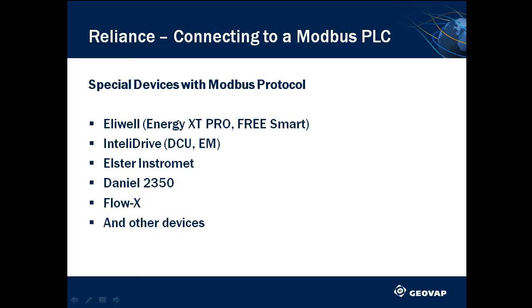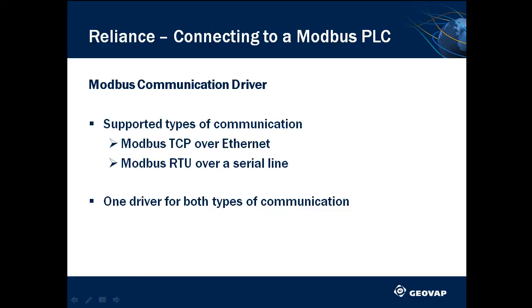As you will see later, these subtypes can be specified after adding a device of type Modbus in the device manager. In the Reliance system, the Modbus communication driver supports both types of communication: Modbus TCP for communication over Ethernet and Modbus RTU for communication over a serial line. By purchasing a license for the Modbus communication driver, you can use both types of communication at the same time.